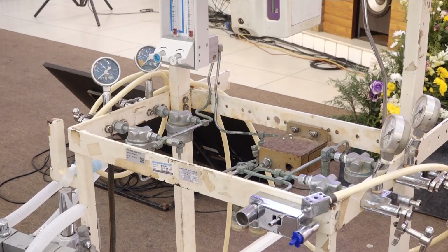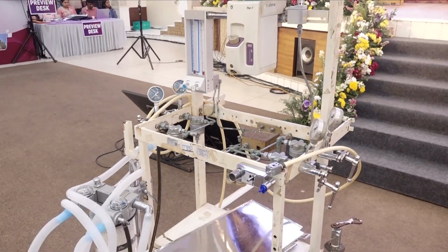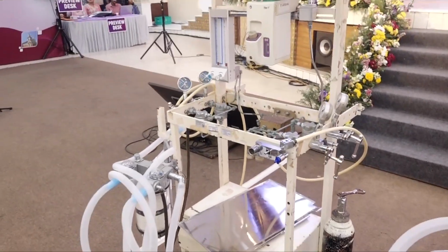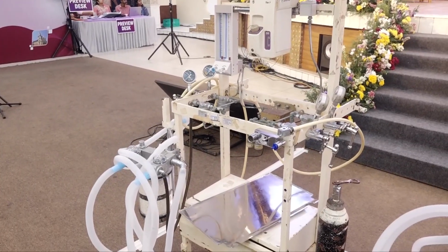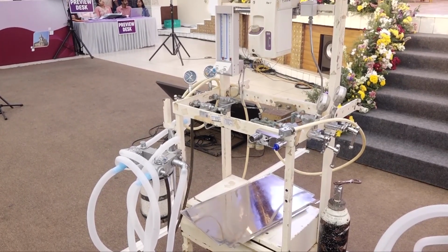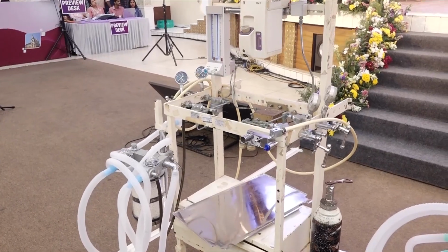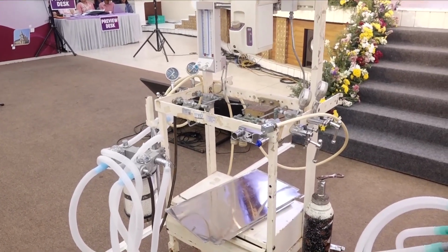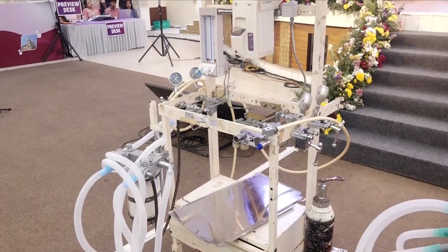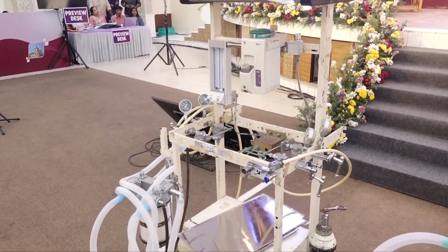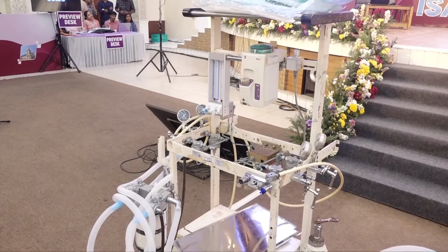You have to know about critical temperature also. Many times you will be asked what a critical temperature is. Critical temperature is that temperature above which a matter cannot be compressed into its liquid state. Below its critical temperature, matter can be compressed into its liquid state. Nitrous oxide's critical temperature is 36.5 degrees centigrade, so it remains a liquid at room temperature, and what the pressure gauge shows you is actually the vapor pressure. So you have the high pressure circuit with cylinder pressures of nitrous oxide 750 and oxygen 2000 psig.